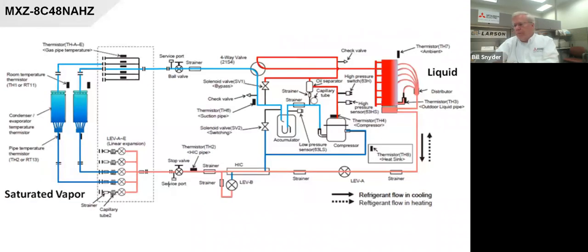Okay, refrigerant system overview. Moving along pretty quick here. This is very similar to what we looked at earlier in this session. We've got the compressor here. We come out of the compressor through the reversing valve. In this case, this is going to the outdoor unit, so we're in the air conditioning mode. Again, you can see all the different thermistors on here. There's also an outdoor air thermistor here someplace. Oh, that's the ambient thermistor, and then there's an entering and a leaving thermistor. Strainers, LEVs, more strainers. That's the heat exchanger going through to another strainer, another thermistor here, through the stop valve or service valve on the outdoor unit.